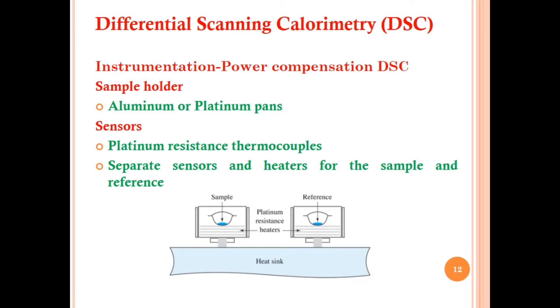The other type of DSC is power compensated DSC. This is a simpler instrument compared to heat flux DSC. The sample holder uses aluminum or platinum pans — two pans, one for the sample and one for the reference. Platinum resistance thermocouples are used as sensors; separate sensors are needed for both the sample and the reference.